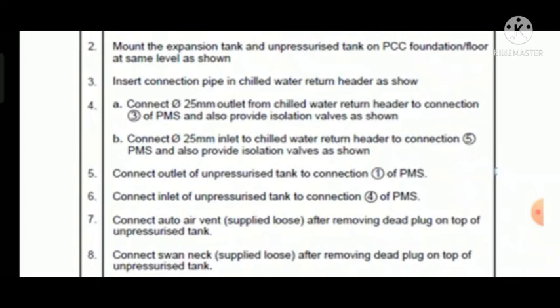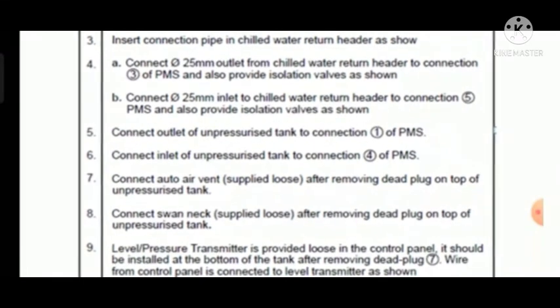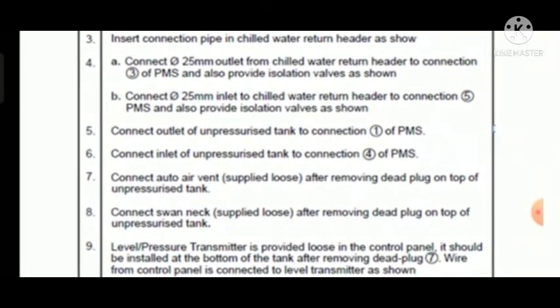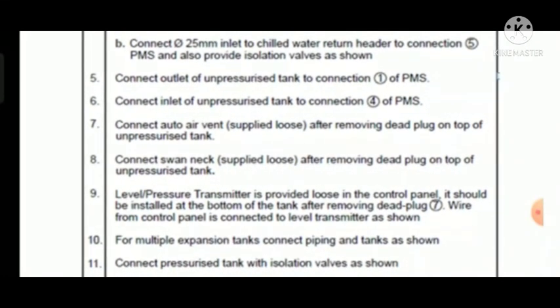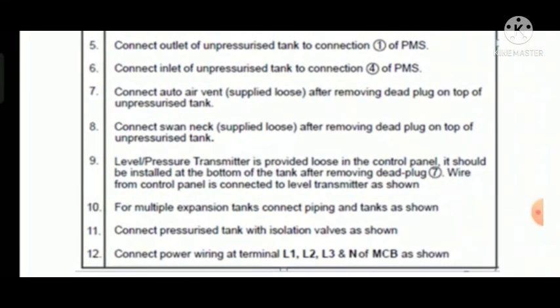The pipes shall be connected accordingly as shown in the diagram. You can see here also that the outlet of the unpressurized tank should go to port number 1 of the pumping set. If you follow this instruction, it is very clear. The air vent, as explained, you also need to fix on the unpressurized tank. Then the swan neck we also need to install on the unpressurized tank. Then the transmitter: I recommend that you connect the level transmitter only at the time of commissioning, otherwise there are chances of the cable getting damaged.